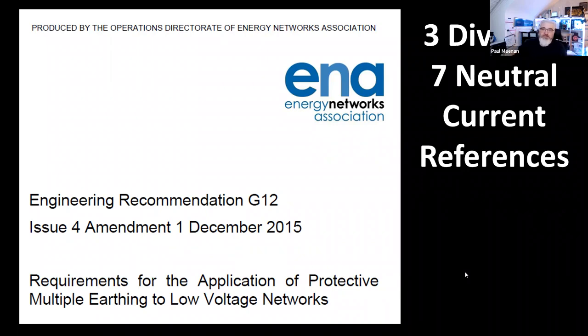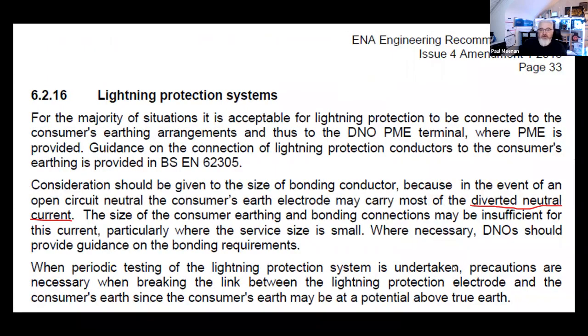Moving on and just skimming through these, Dave, if you look at the section on lightning protection, it talks about consumers' electrodes carrying most of the diverted neutral current, which is really interesting because a couple of years ago, Dave, and everybody, we were referencing foundation earthing or electrodes installations. Now, one of the considerations and worries I have, if we start banging electrodes in everywhere, are we going to mask the issue of diversion?